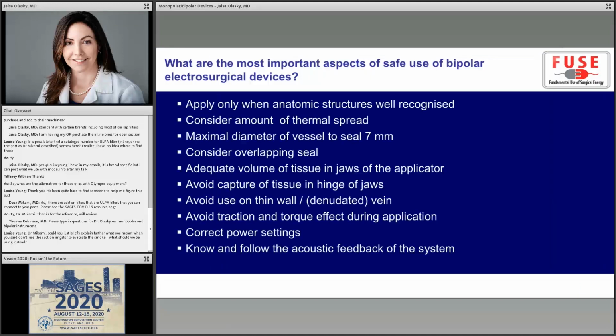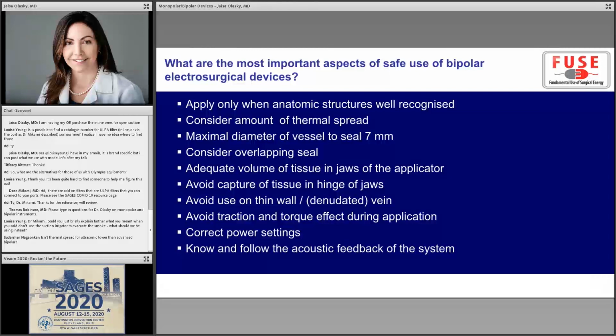And then just some final safety aspects. We've covered most of these, but just to hit the key points again, you want to consider the thermal spread. 7 millimeter vessels or less are appropriate. Adequate volume of tissue in the jaws and avoiding the hinge of the jaws, that's a good one. If you look at your advanced bipolar instrument, there will be 2 hash marks, one towards the jaws and one towards the tip. That is the area that it's working in, and so you really don't want to take so much tissue that it's beyond that, or shove it so far into the hinge that you have tissue on either side that's not getting the full energy.